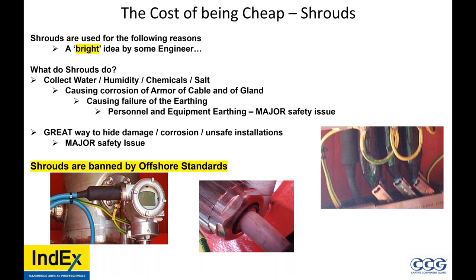Now, some people may say, well, I put a drain at the bottom. Water will still stand on the gland. Chemicals will still stand on the gland. What do these cause? Well, it causes corrosion of the armor of the cable and the gland, which causes failure of the earthing. Personnel and equipment earthing, if this fails, like we talked about the gland that corroded and broke away, that's a major safety issue. It's also a great way to hide the damages, corrosion, and unsafe installations.